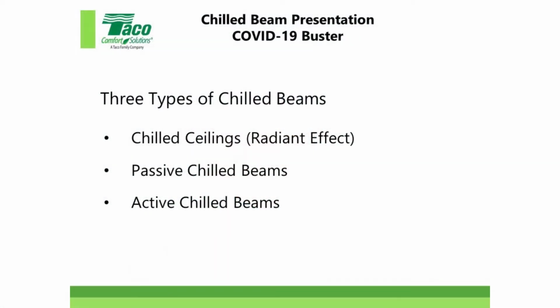But again, others would. Keep in mind, I don't sell the chill beams, so that's something to consider. And then there are some out there with drain pans that can be considered, so we'll talk about that when we go into some of those. There are favorable ones and less favorable ones, something to consider as you look at it. There are three types of chill beams, or radiant cooling type systems. First is the chilled ceiling, and this started in Europe. A lot of the buildings a long time ago weren't air conditioned, so all they did was put some pipe up above the ceilings, right? They didn't have room to put anything up there, so that's really what a chilled ceiling is, and I'll show you a picture of that very shortly.